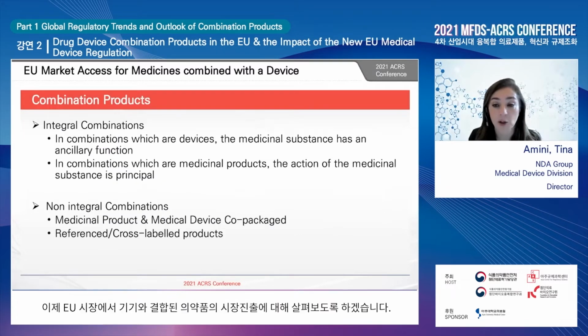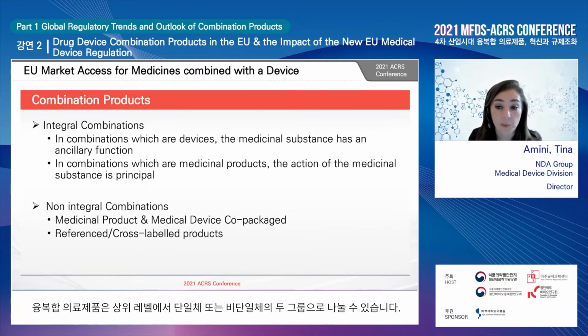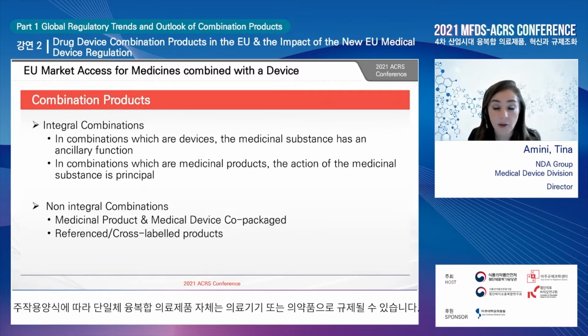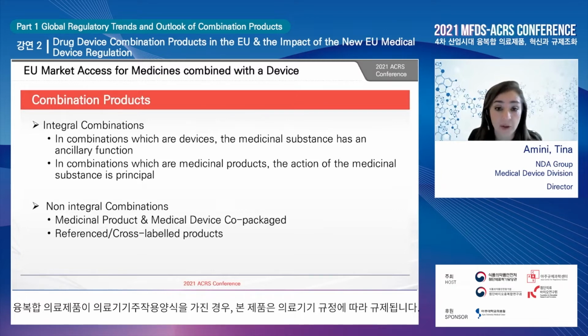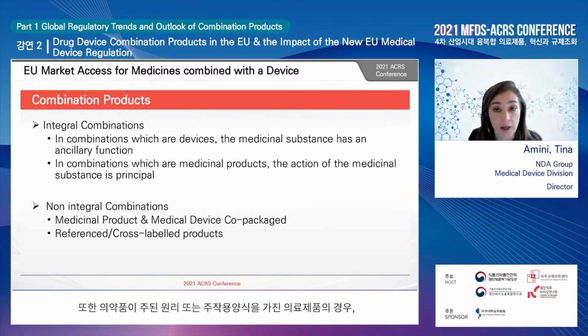So now let's look at the EU market access for medicines combined with a device. Combination products can be put into two groups at the top level: integral or non-integral. Integral combinations, depending on the primary mode of action, can be regulated either as a device or as a medicinal product. If the primary mode of action is the device, then the combination is regulated under the medical device regulation. And for those where the medicinal product has the principal or primary mode of action, the whole combination is regulated as a medicinal product.